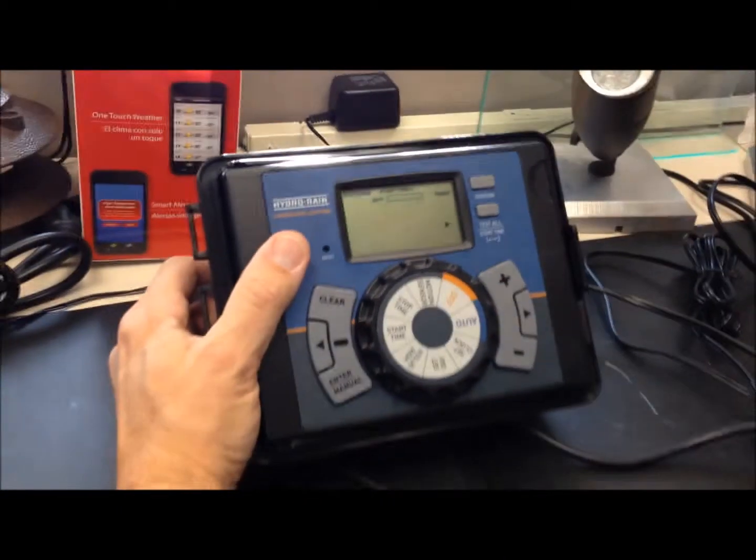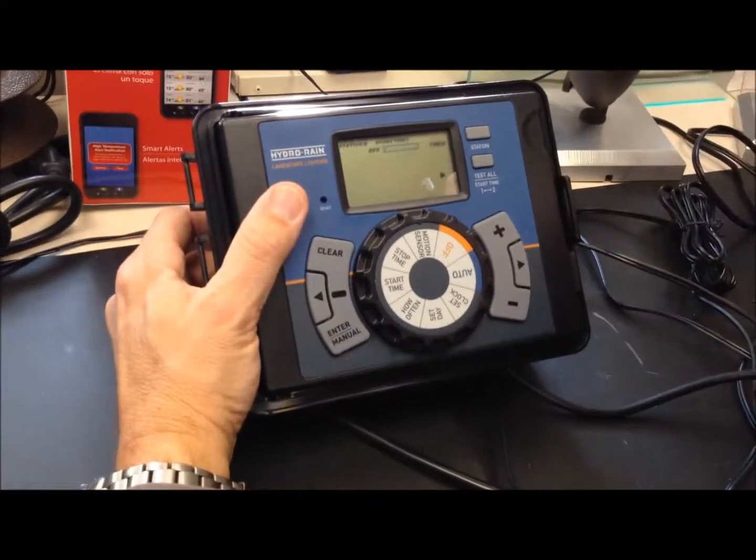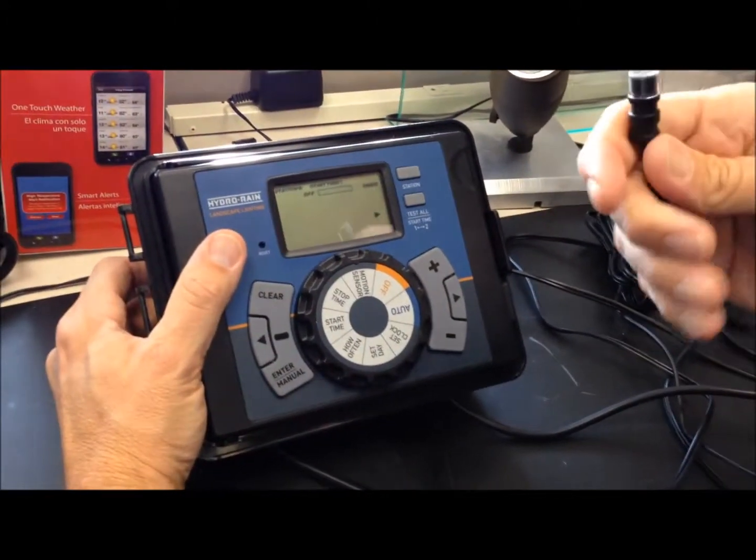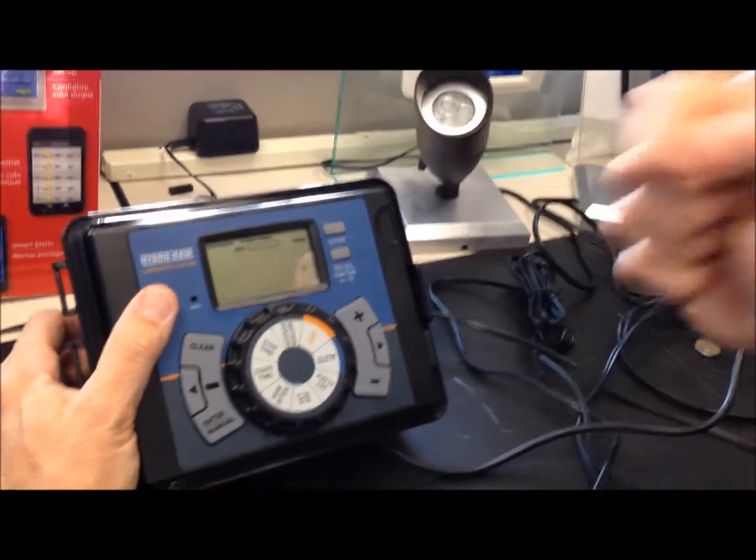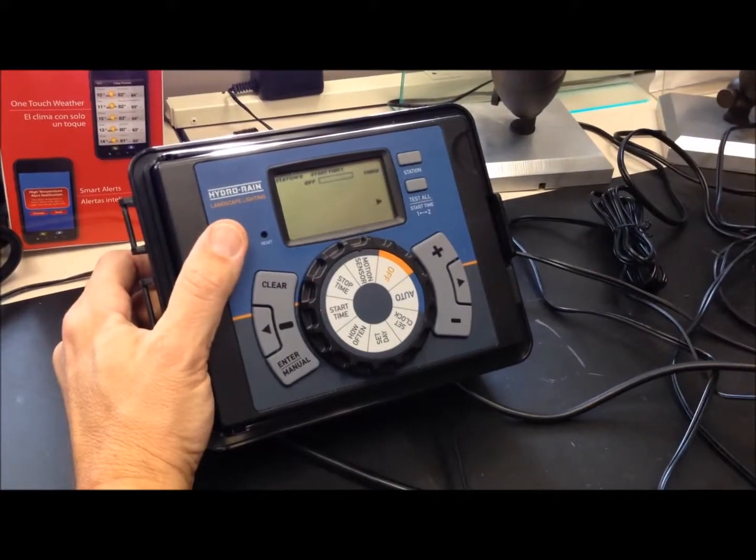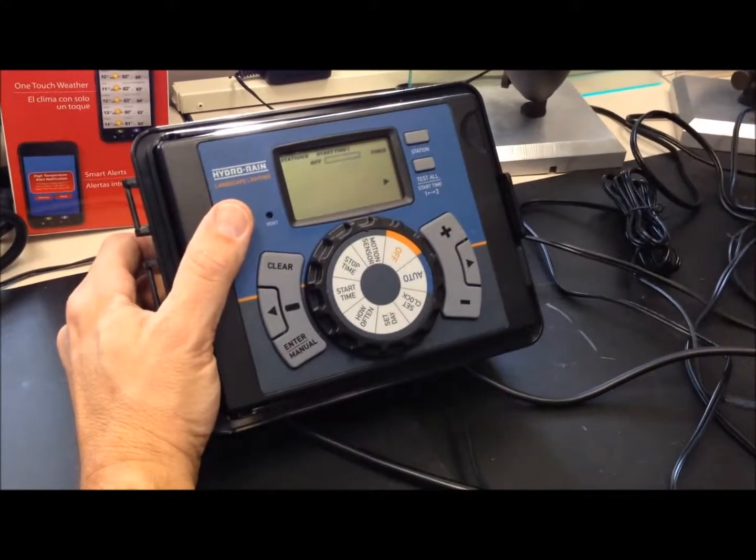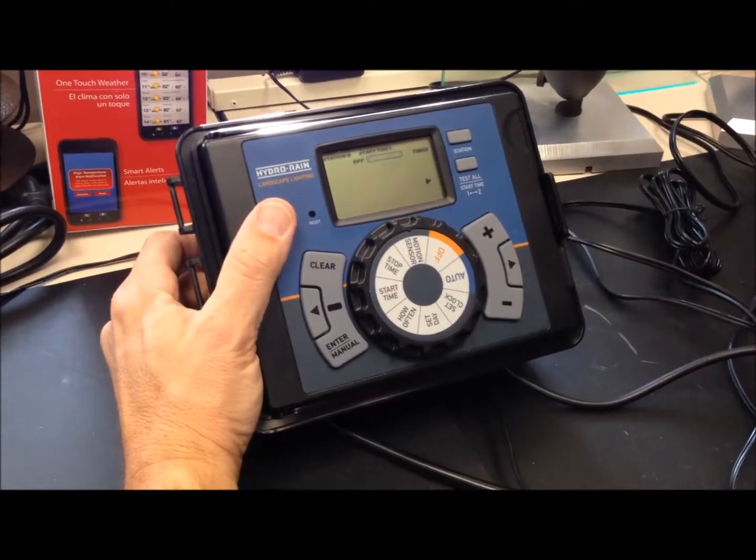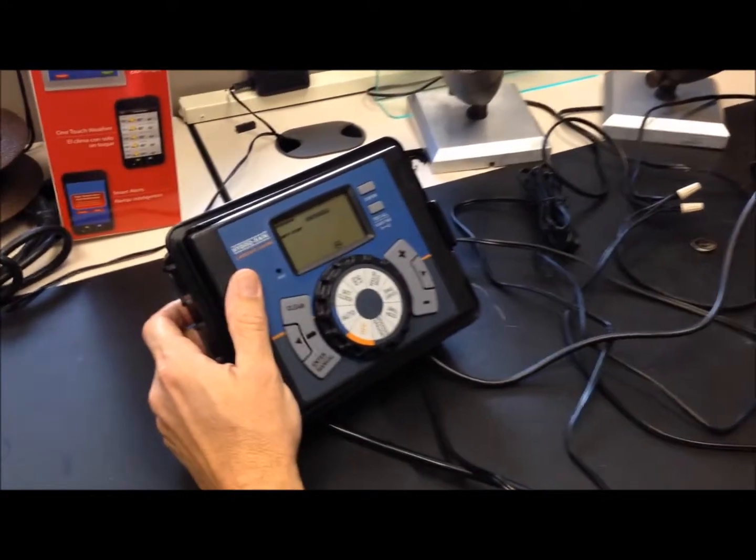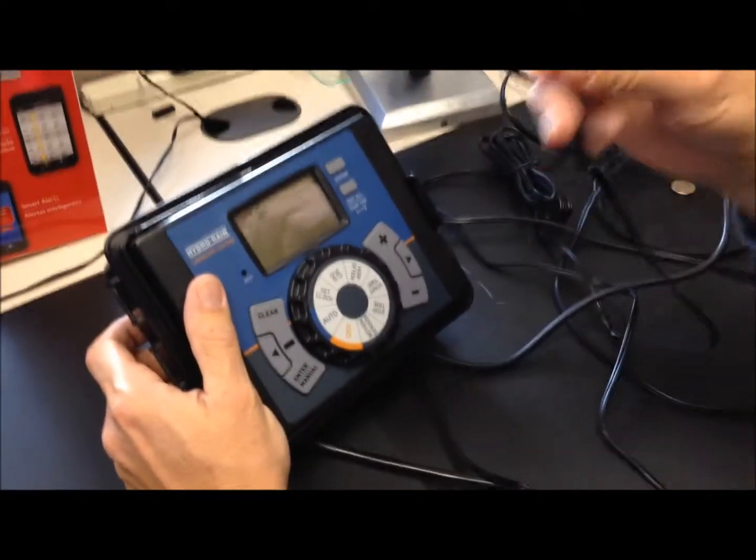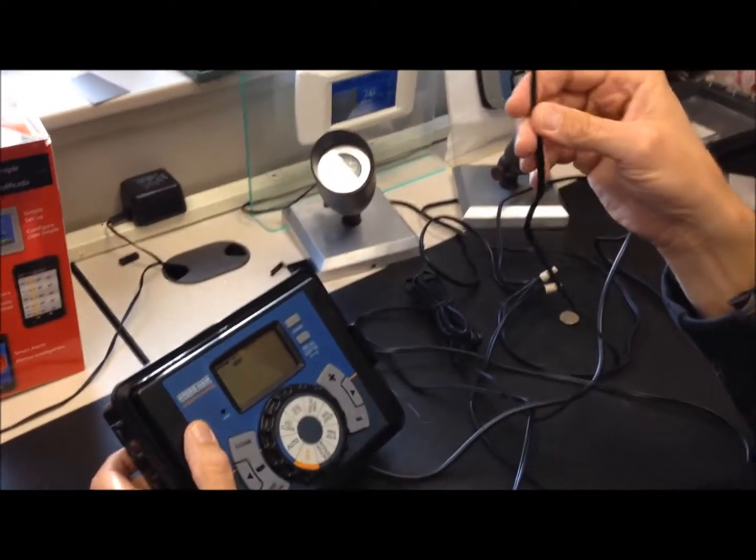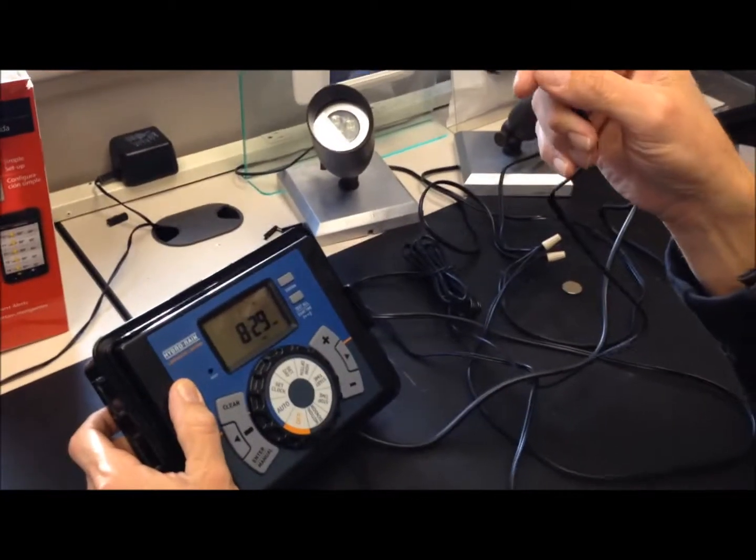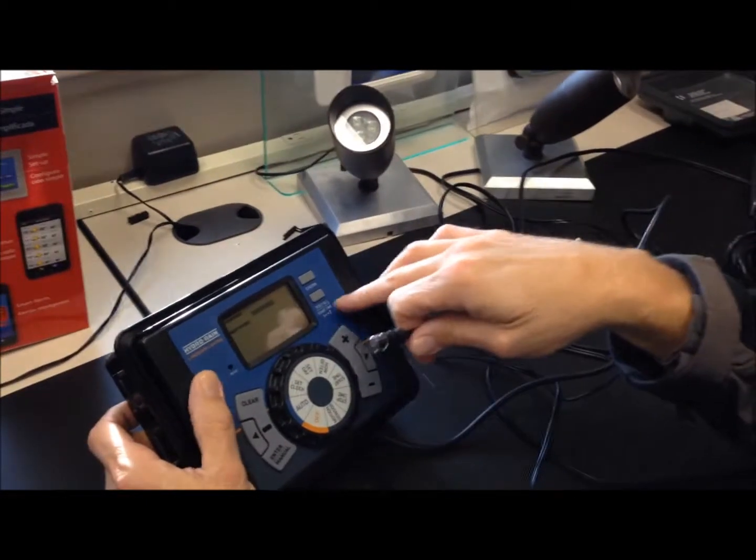Now, one thing to know if you're testing the system, if you take the photocell and cover it, you're not going to get an immediate indication that the photocell is seeing dark. It takes several minutes. So just a reminder, it takes three to five minutes for the photocell to indicate light or dark.